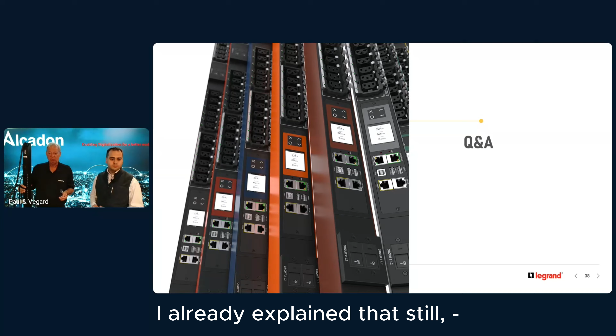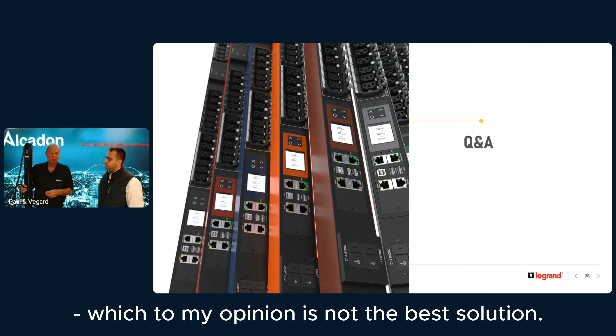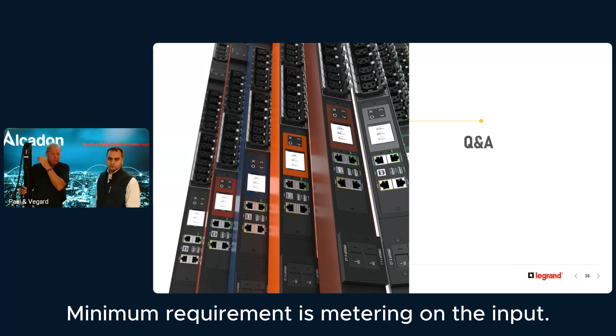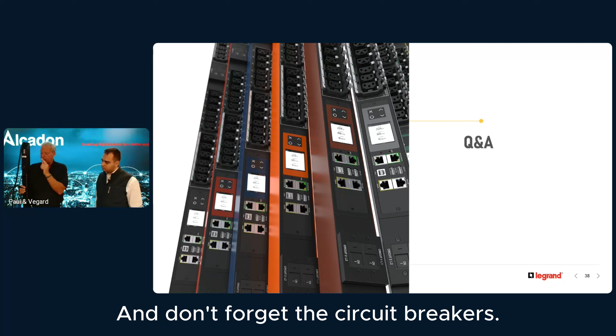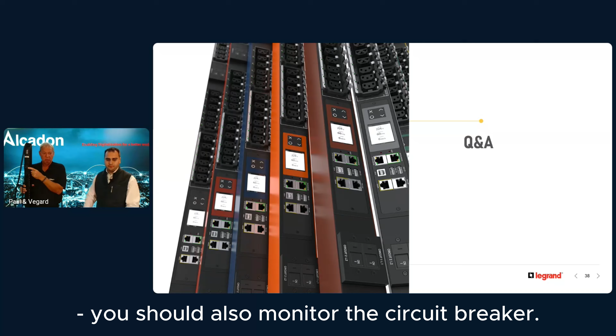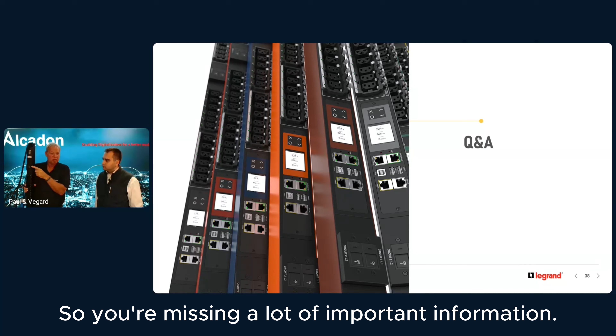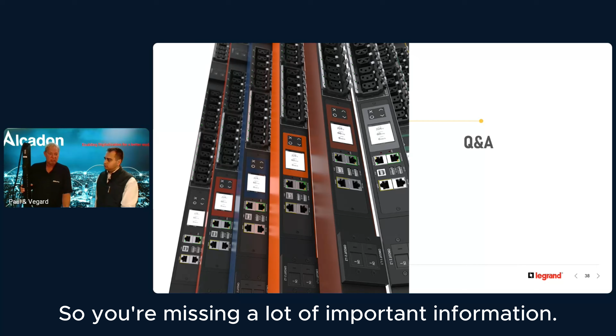Still, companies are investing money on basic PDUs, which in my opinion is not the best solution. Minimum requirement is metering at the input. Better even is measuring at the outlet level. And don't forget the circuit breakers. If the PDU has a circuit breaker, you should also monitor it. There are a lot of cheap PDU manufacturers that offer input and outlet metering, but they don't measure the circuit breaker, so you're missing a lot of important information.